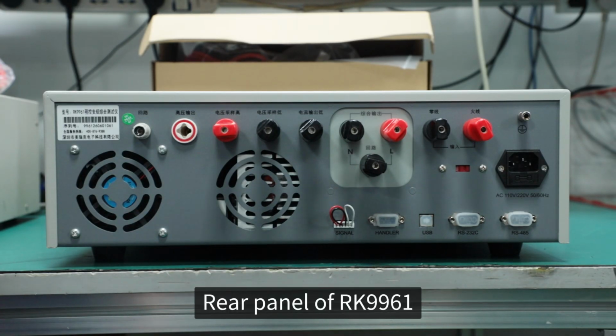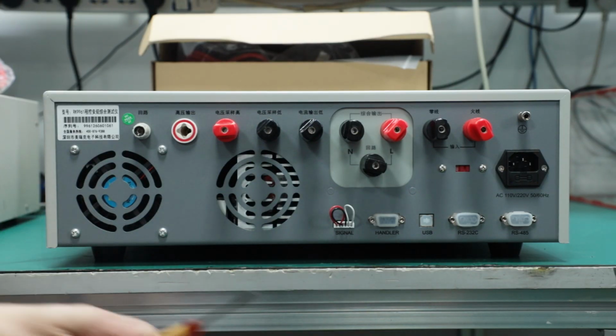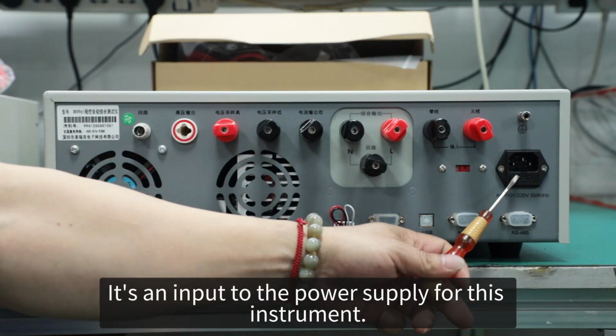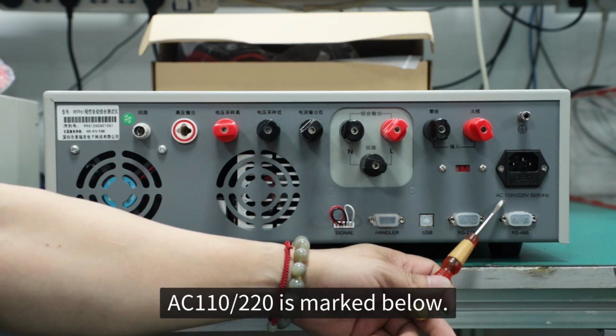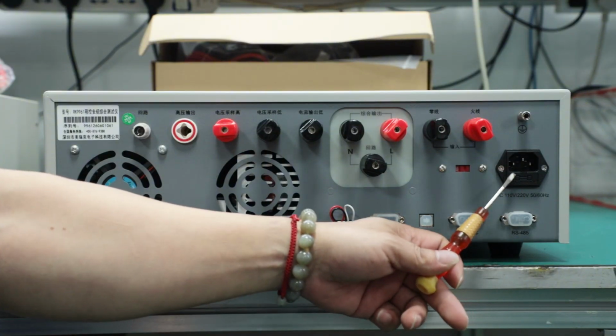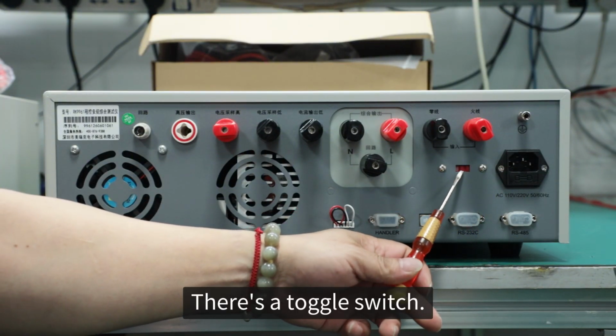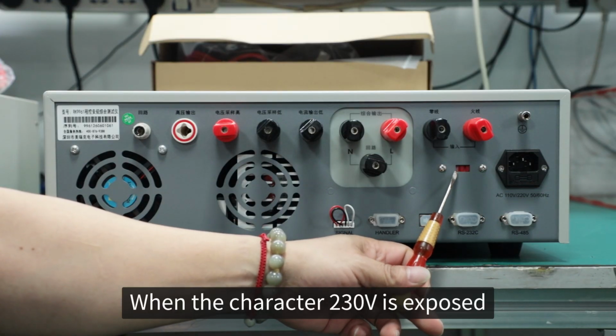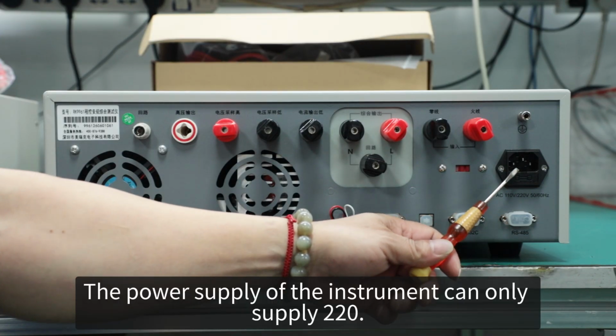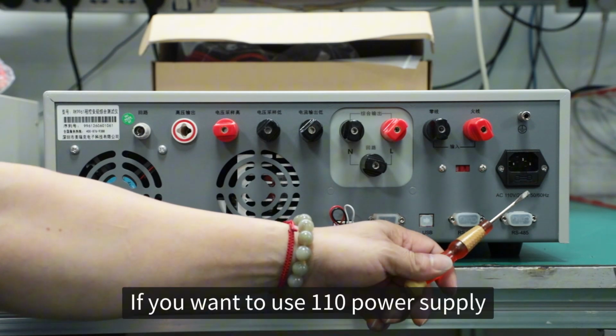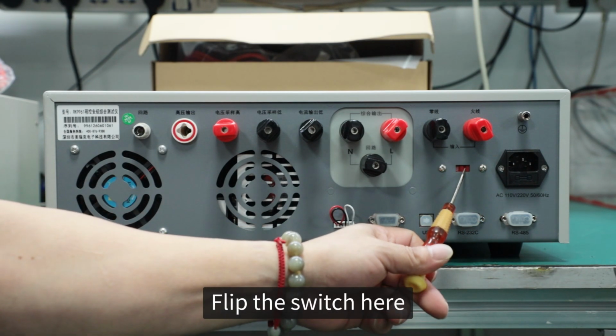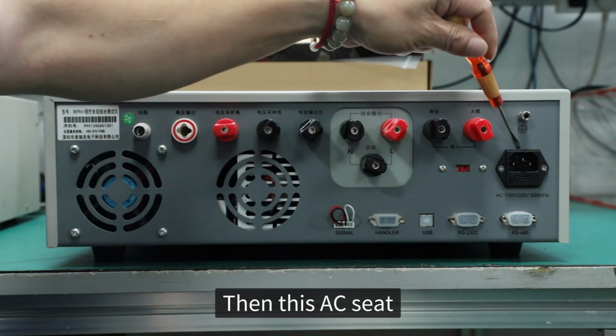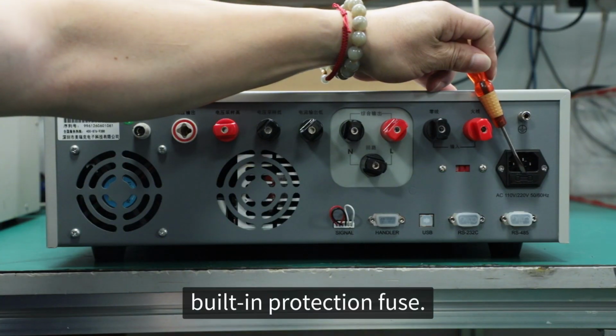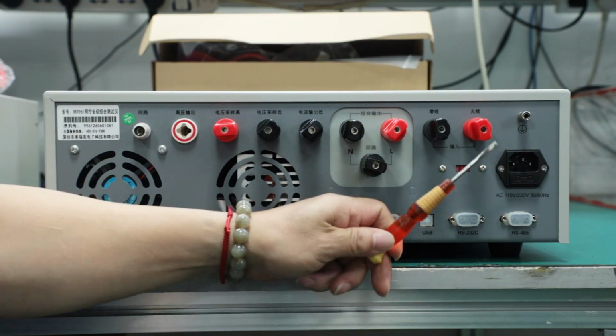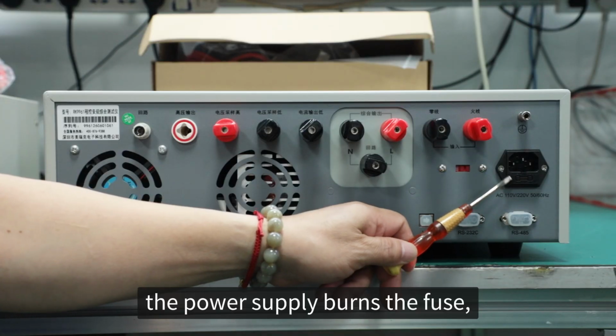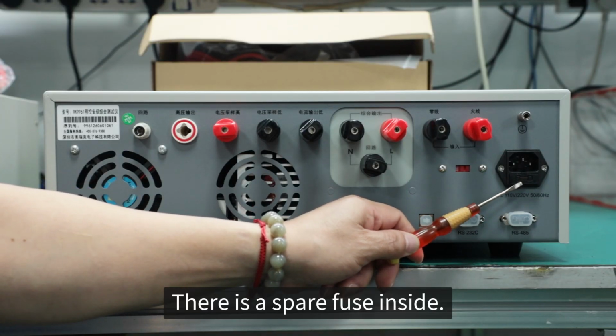Now, I will introduce to you the rear panel of the RK9961. Here is the input for the power supply of this instrument, also known as the AC socket. AC110-220 is marked below, so there are 2 power supply methods. There's a toggle switch; when the character 230 volts is exposed, the instrument can only be supplied with 220. If you want to use 110 power supply, flip the switch here and switch it to 110. Then this AC socket has a built-in protection fuse. If any fault causes the power supply to burn the fuse, just pry this out. There is a spare fuse inside.